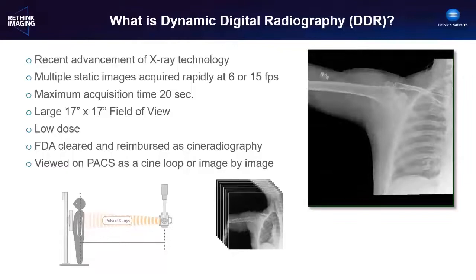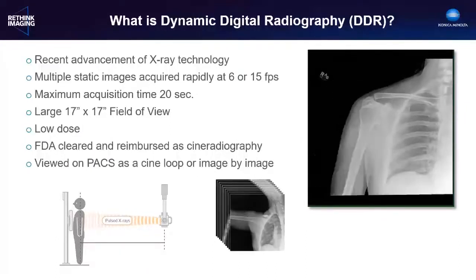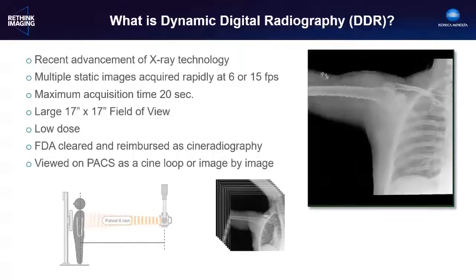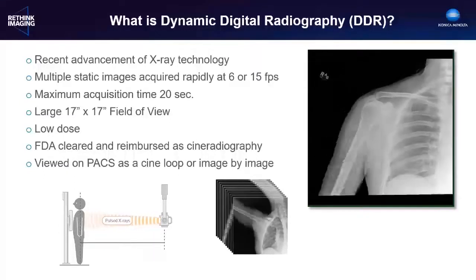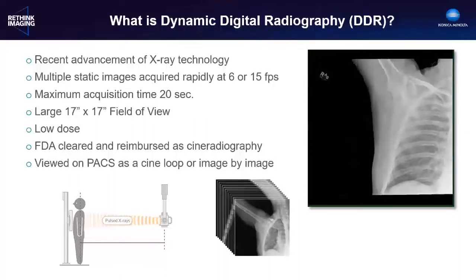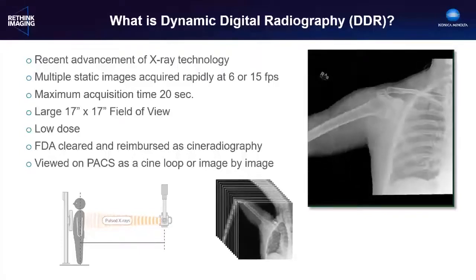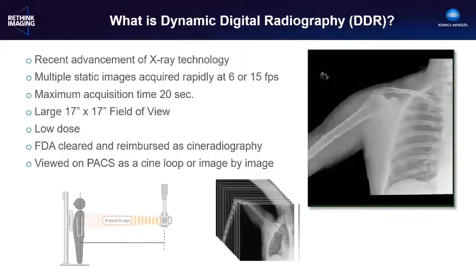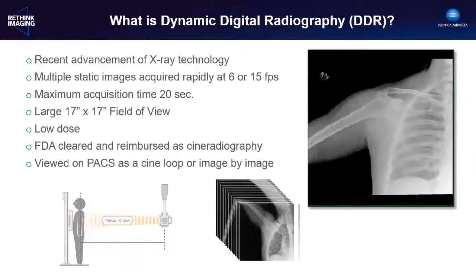Dynamic digital radiography, or DDR, is a recent advancement cleared by the FDA in late 2018 that enables the acquisition of a series of static images at 6 or 15 frames per second. With current implementations, the maximum acquisition time is 20 seconds and it can be acquired over the full 17 by 17 inch field of view of a large format flat panel digital detector. The system requires a pulsed x-ray source to ensure very low dose. For a 15-second, 15-frame-per-second chest acquisition, the typical dose is just over seven microgray per frame for a total of about 1.5 milligray. The resulting image datasets are viewed as standard DICOM objects on a PACS, either in a cine loop or paged through frame by frame. Individual frames can be extracted for archiving or further analysis, just as a conventional static image would be.